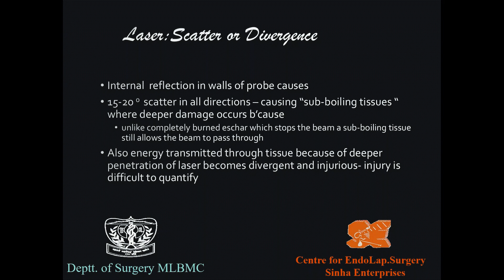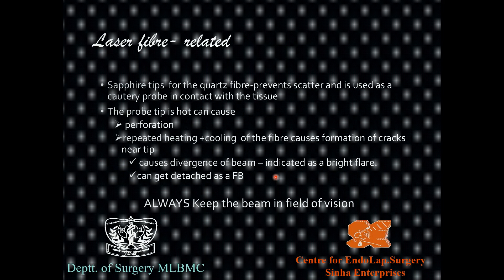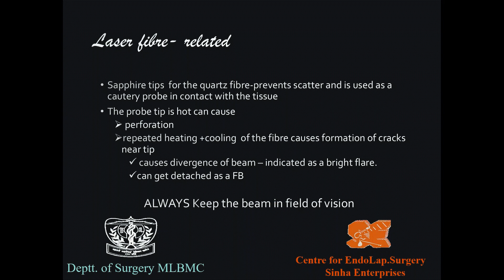Laser fiber-related complications include a sapphire tip that delivers energy to the area; if it breaks completely the tip is lost, but if cracked, the crack allows the laser beam to escape sideways. Repeated heating and cooling of the fiber causes crack formation; this crack causes beam divergence indicated as a bright flare, and the detached tip can become a foreign body. Always keep the laser beam tip in your field of vision.